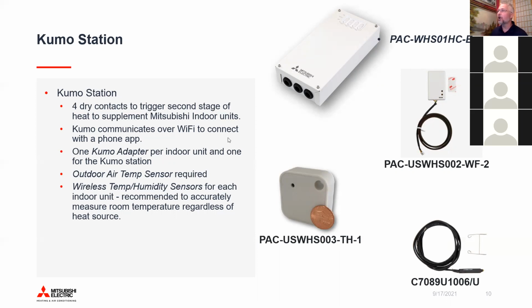Okay, and there are other accessories associated with it. So you have these Bluetooth wireless remotes that sense both temperature and humidity. That should be included for every zone that you plan to control. And it's not only because you get a better room temperature for the heat pump aspect of it, but it also allows you to place that temperature sensor somewhere in the room where it's going to be both a good place to sense the temperature for the indoor unit, but also an excellent location to sense the temperature for your backup heat source.